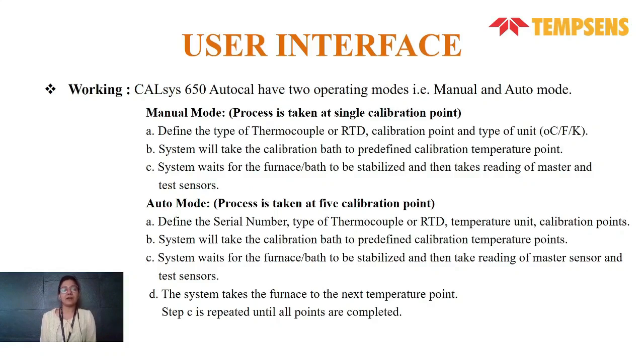Okay, let's talk about its working. Calsys 650 has 2 operating modes, manual mode and auto mode. In manual mode, we can define the type of thermocouple and RTD and define its unit type like centigrade, Fahrenheit, Kelvin. When we put in our set temperature, we wait for furnace stabilization. After the furnace is stabilized, we take out our master and test sensor readings.